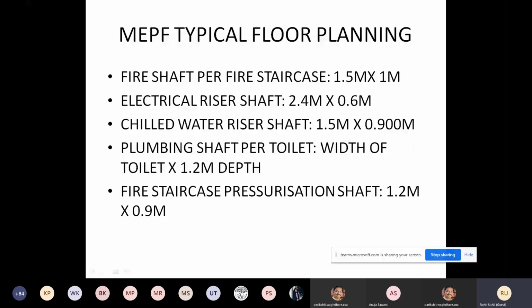This is very important because it will be very critical to all of you who are designing a typical floor, and you need to provide space for these MEP utilities, these shafts, without which it is not possible to convey power and the services to the floors that you're designing. So typically a fire shaft requires a space of 1.5 meters by 1 meter. An electrical riser shaft requires a space.